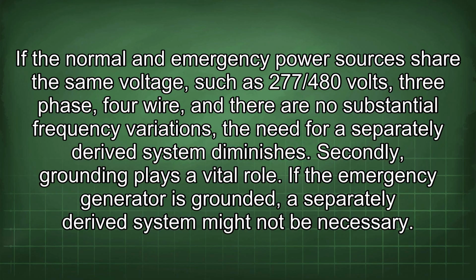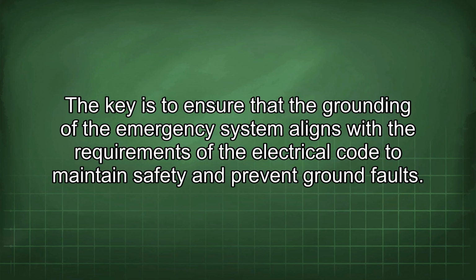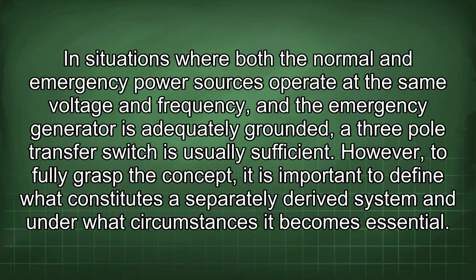Secondly, grounding plays a vital role. If the emergency generator is grounded, a separately derived system might not be necessary. The key is to ensure that the grounding of the emergency system aligns with the requirements of the electrical code to maintain safety and prevent ground faults. In situations where both the normal and emergency power sources operate at the same voltage and frequency, and the emergency generator is adequately grounded, a 3-pole transfer switch is usually sufficient.